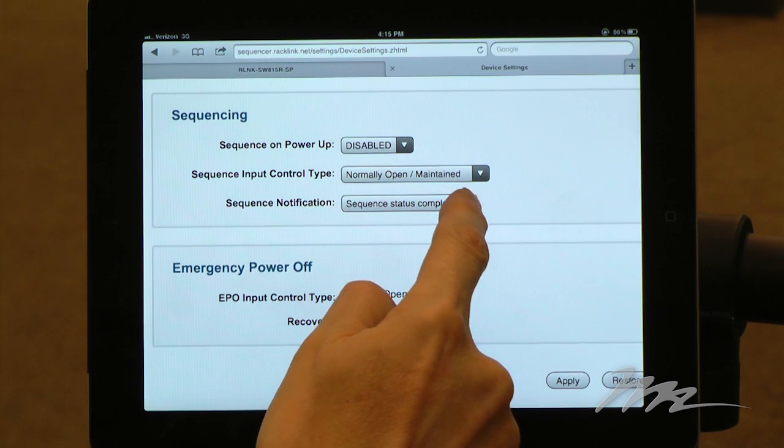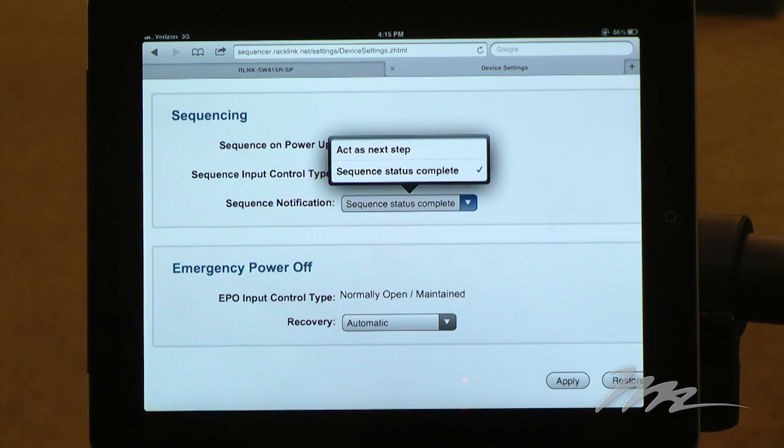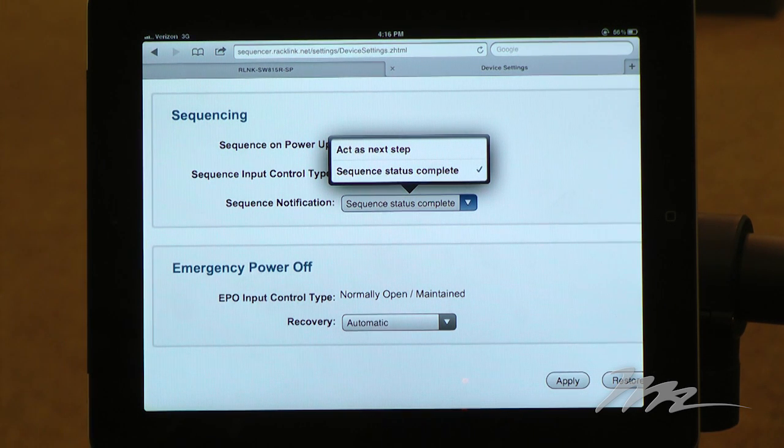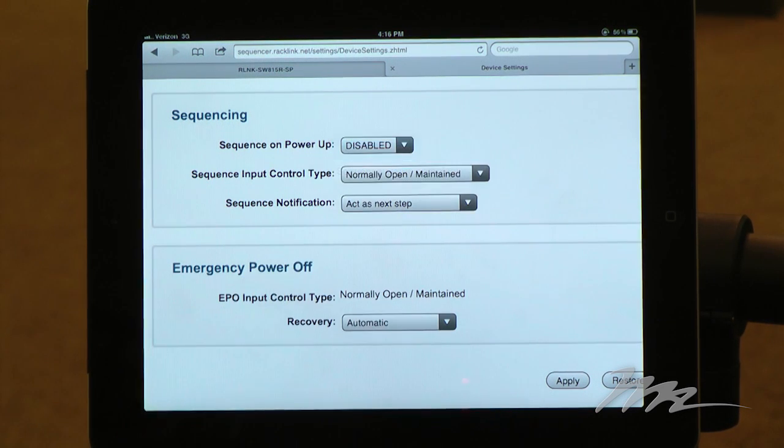You can decide whether you want to use the sequence notification dry contact either as a status complete notification or Act as Next Step. In selecting Act as Next Step, you can use the last sequence step to initiate or cascade any number of additional sequence devices.